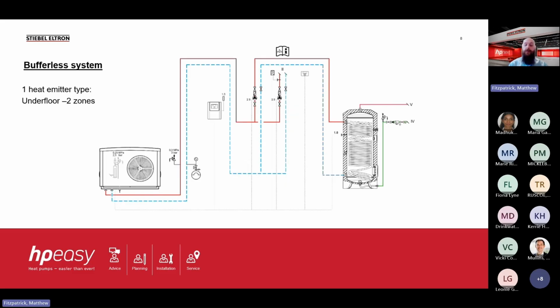So I've mentioned the phrase bufferless system. You may have heard it before in the industry. Effectively, it means there is no buffer cylinder. The heat pump is supplying directly to the underfloor or radiators. Now, in this type of system, we can't mix and match heat emitters. Again, going back to the previous comment that we need hydraulic separation, and we also need a variable in temperatures, two different temperatures. So it can only supply underfloor or radiators. And in most cases, it needs to be kept as open loop.